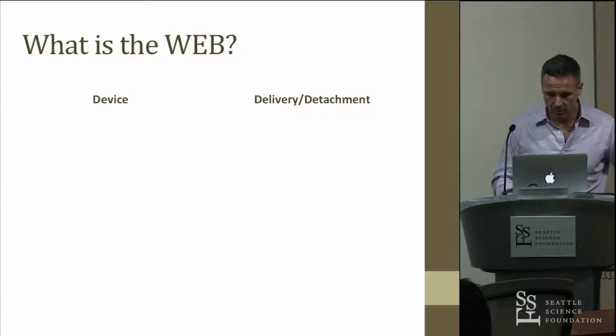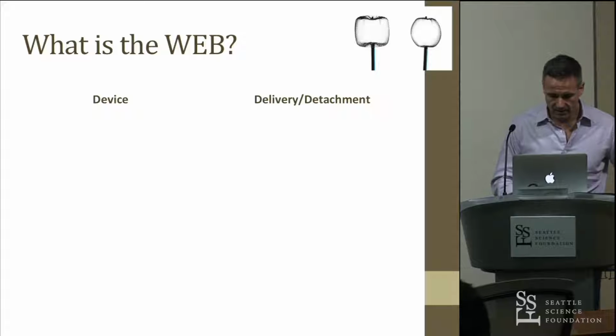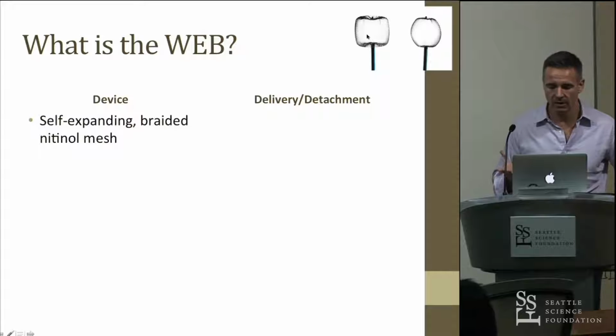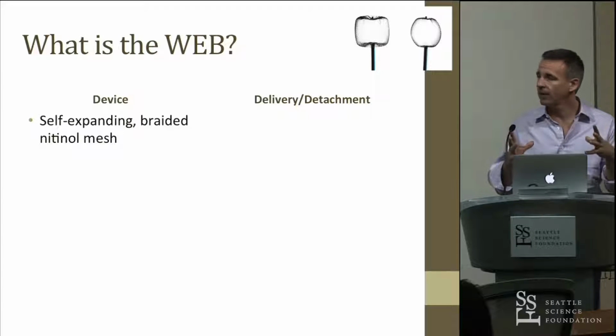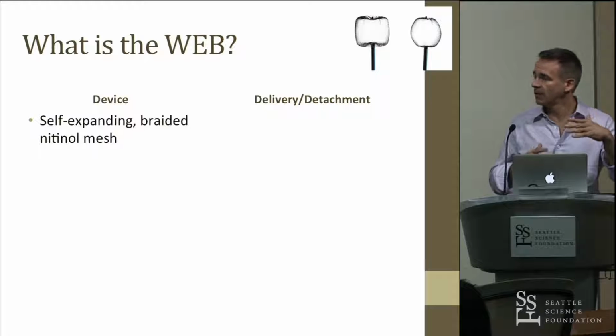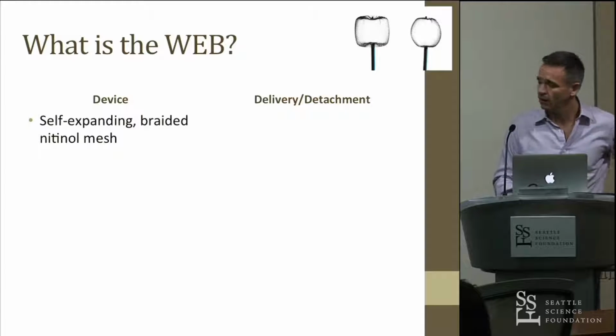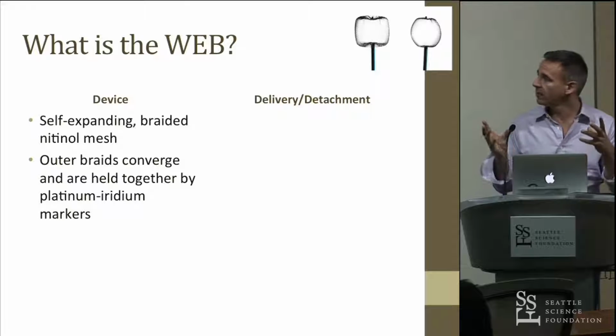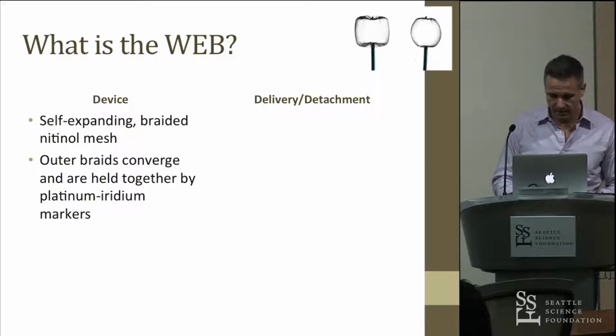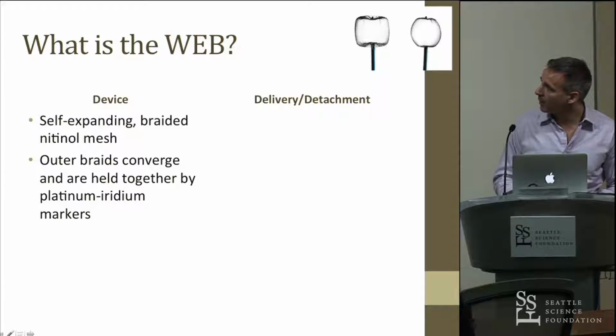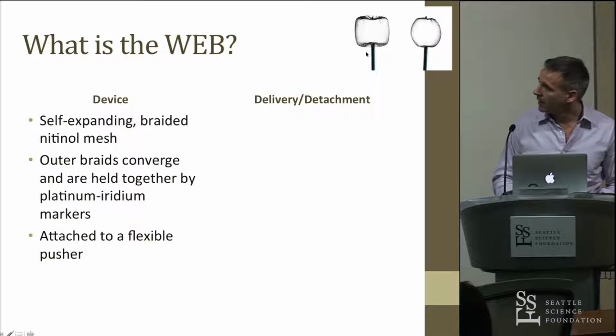What is the WEB, or the Woven EndoBridge? So it looks like this. There are 2 shapes of it that are now in common use, but basically it's a self-expanding braided nitinol mesh that's shaped either like a ball or like what's called an oblate spheroid, which basically is a ball where you cut the 2 ends off the ball. And the outer braids are held together at the base by markers made out of platinum iridium. So you have these very fine nitinol strands that are micro-braided into these platinum iridium markers that hold them together. And that's attached to a flexible pusher, so it's pushed through a catheter just like any other coil or stent.